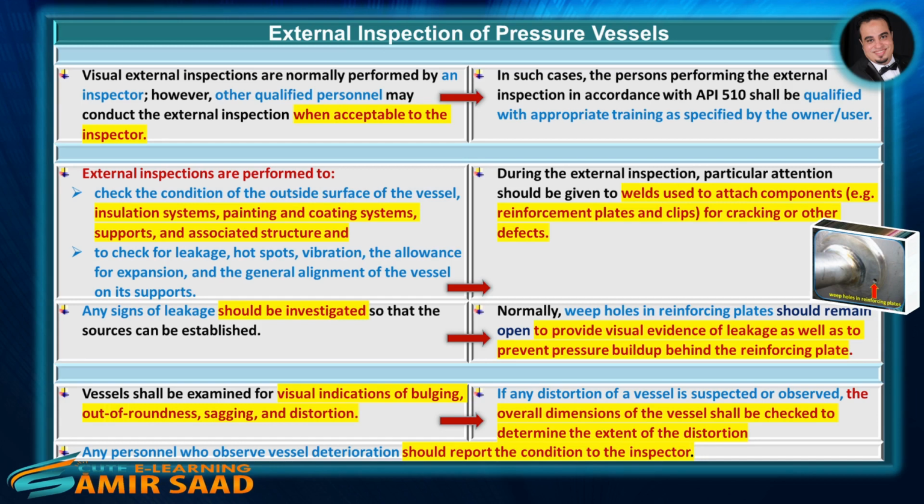Any signs of leakage should be investigated so that the sources can be established. Normally, weep holes in reinforcing plates should remain open to provide visual evidence of leakage as well as to prevent pressure buildup behind the reinforcing plate.